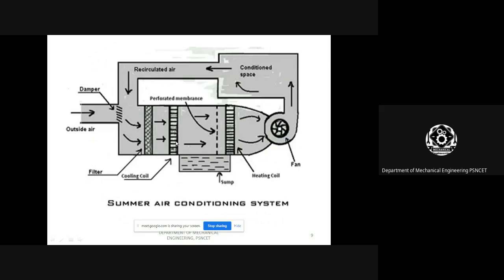As the air is cooled continuously, the water particles in the air are collected in the sump by means of the perforated membrane. Passing through the perforated membrane, the water particles are condensed and collected in this sump. So now the air is much cooler than the atmospheric air. Again, it is heated by means of the heating coil. What is the purpose of cooling and then again heating? The air is cooled to a lower temperature, and once again it is heated by means of this heating coil.